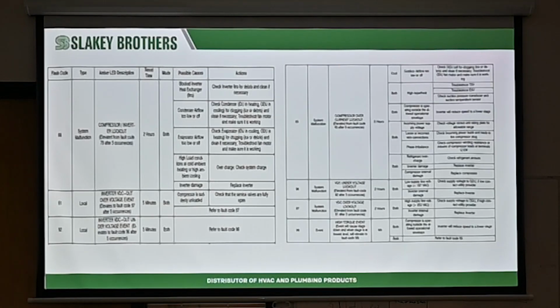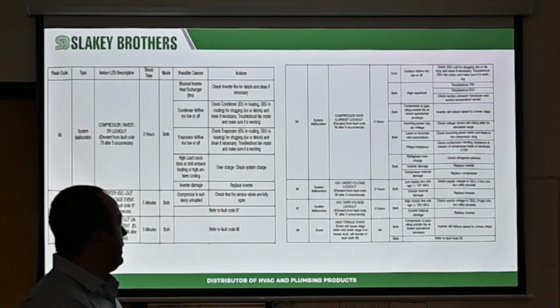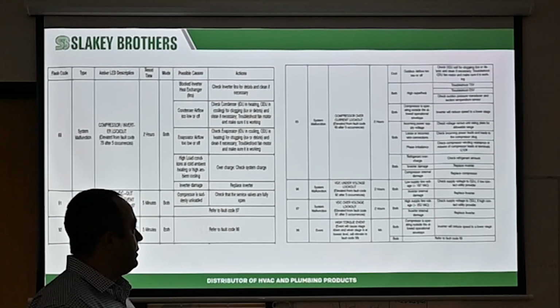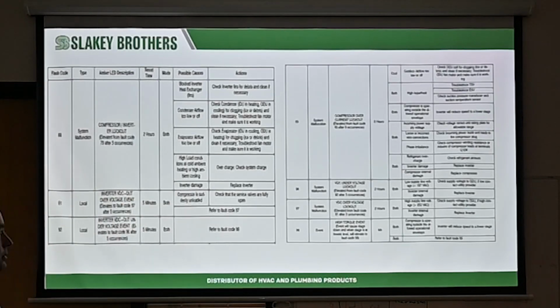But when you look at these manuals, and you don't really find this stuff on the doors of the units, but this is in the manuals. When you find your fault, it tells you what it is, and then it tells you, well, one is for both heat pump and AC. Some of it only applies to AC only, because these diagnostic codes are the same for both types of units, both the heat pump unit and the air conditioning unit. And then look at your possible repair, possible thing you've got to do.